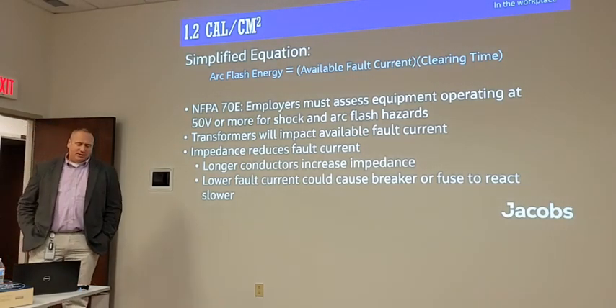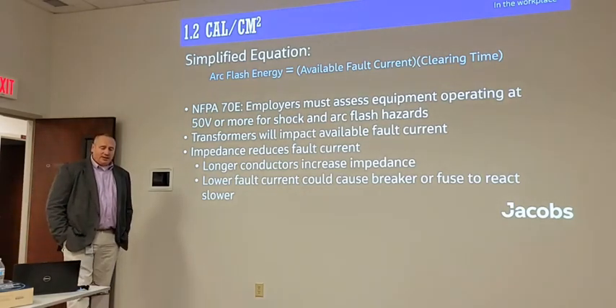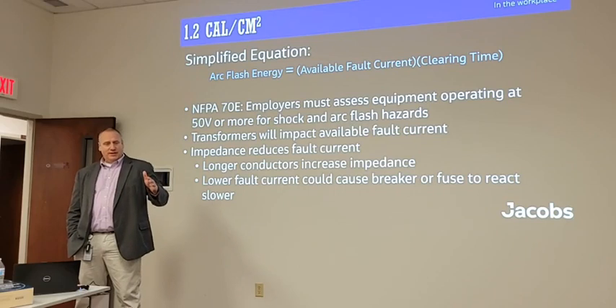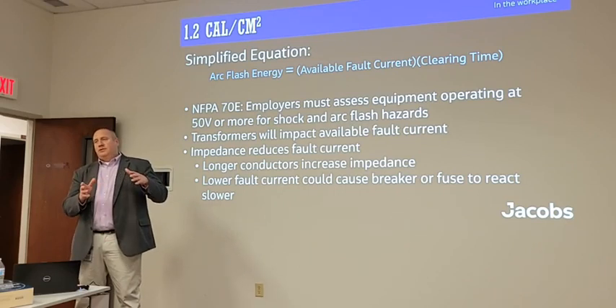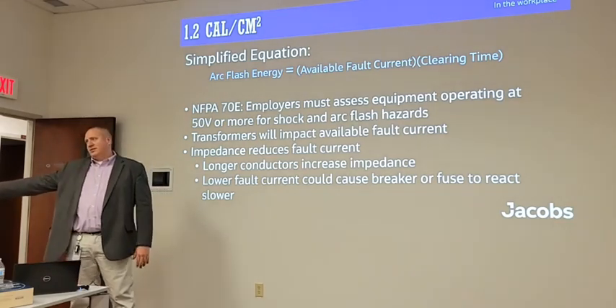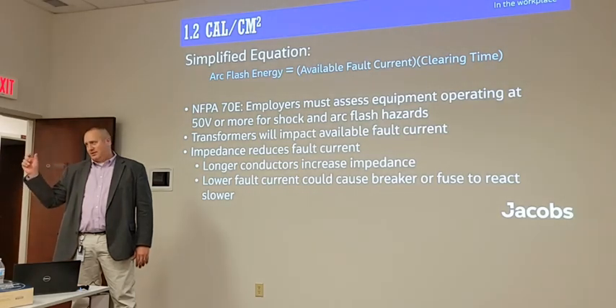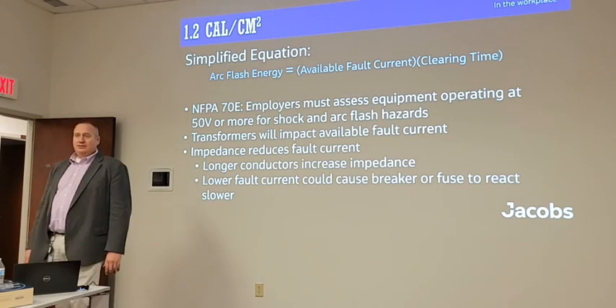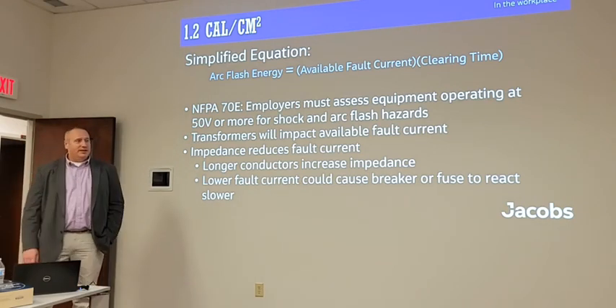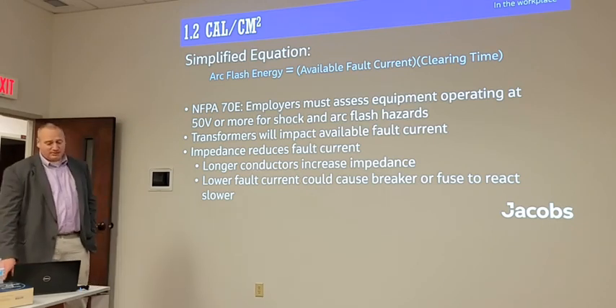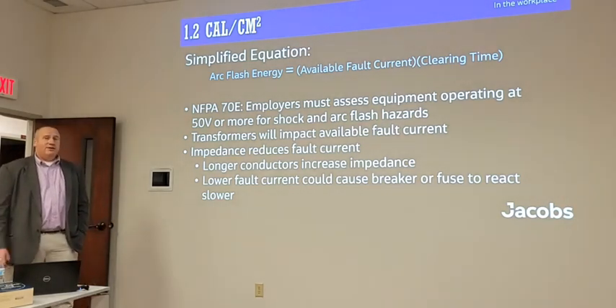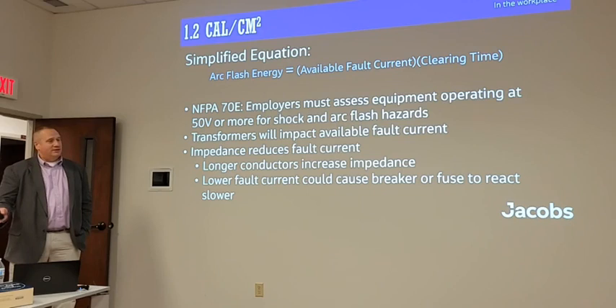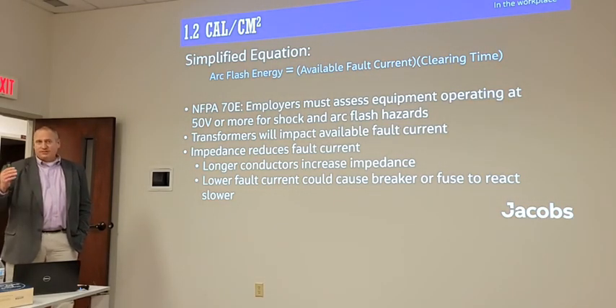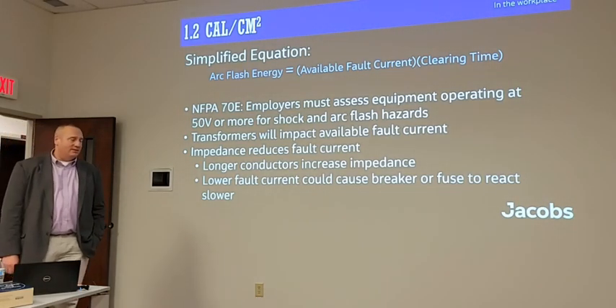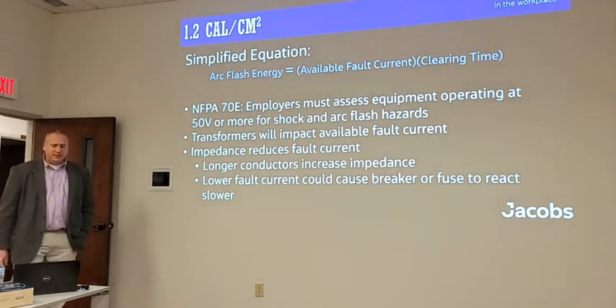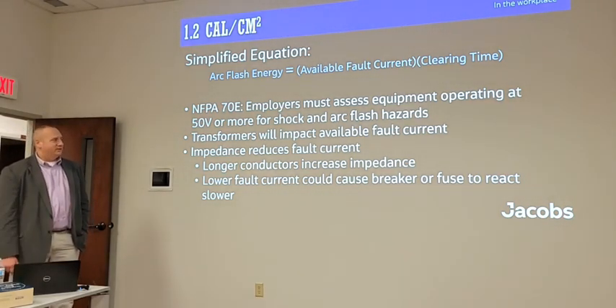This is one that I overlooked for a long time, that you could have a scenario where an overcurrent protective device is right on the edge of the instantaneous trip setting. And if you were to add a very long conductor that adds just enough impedance to where now it's not going to hit that instantaneous current level, then it changes your clearing time, because now instead of instantaneous trip, it moves it into a delayed trip of whatever, depending on the overcurrent protective device. So there could be scenarios, while it's not necessarily all that likely, that adding some impedance into the system can go from a lower arc flash rating downstream to a slightly higher one because of the trip settings. So we can't just assume that if it's 1.2 calories, that the rest of the system's safe downstream of it.